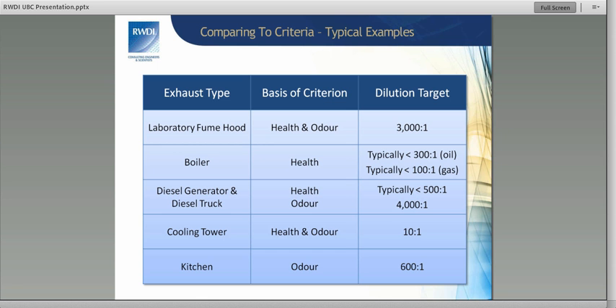These are some common dilution ratios that we deal with for different types of sources. The first one, a very common source, is a laboratory fume hood: 3,000 to 1. We have to dilute an emission 3,000 times before it comes back into an air supply. That's a pretty big number. The reason is, in a fume hood, there could be any number of chemicals used.